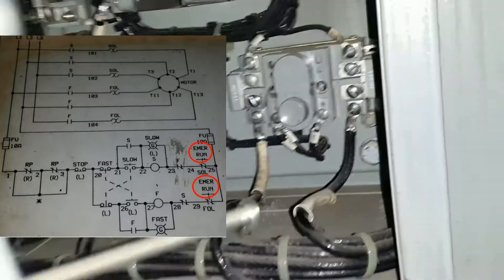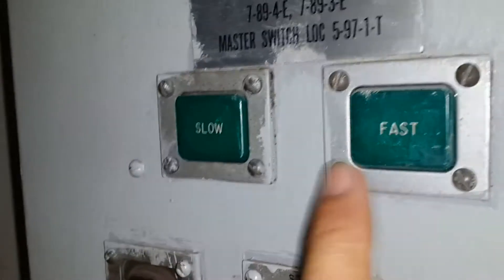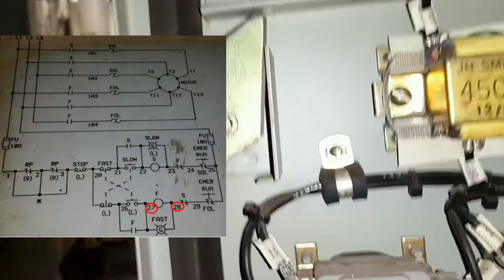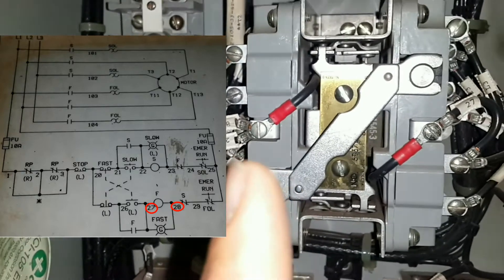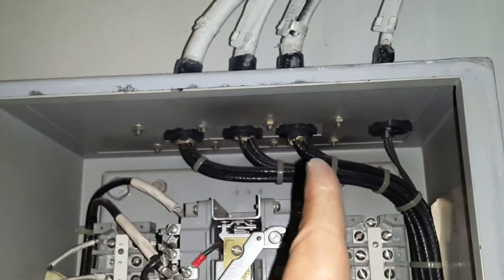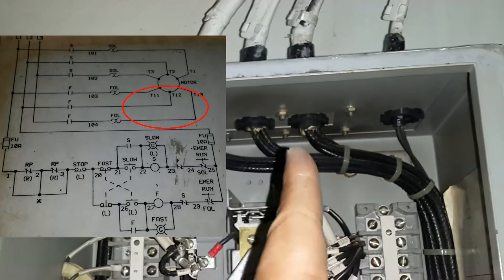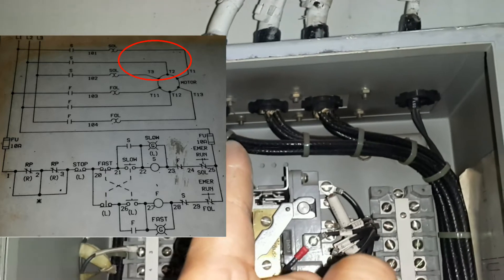Now we don't open to press it, we just simply have this little long screw. As far as the lights, once again this one is the fast, so the fast one over there, look at that, it has the 28 and 27, which also is going to coincide with the same connections of its associated contactor. The bottom contactor is the one that is the fast speed. Now the installer decided to use a certain type of wire: one is power coming in always energized, the other one is going to the fast winding, and the last one to the slow winding.